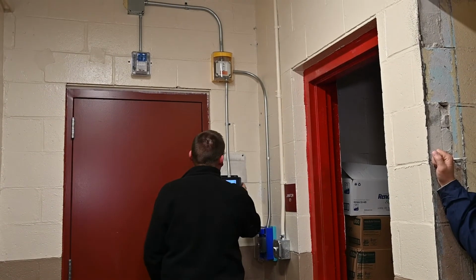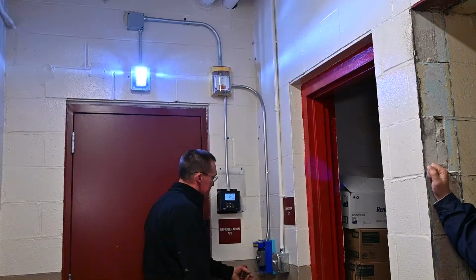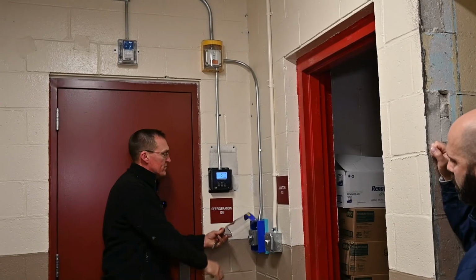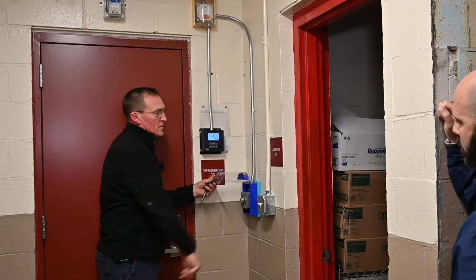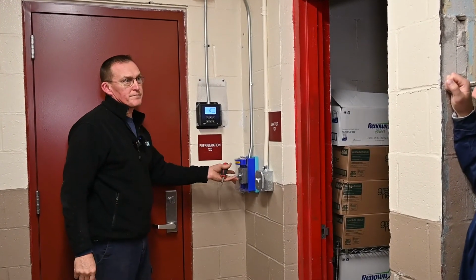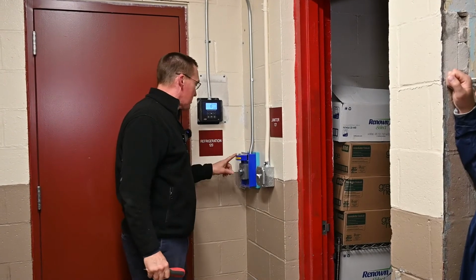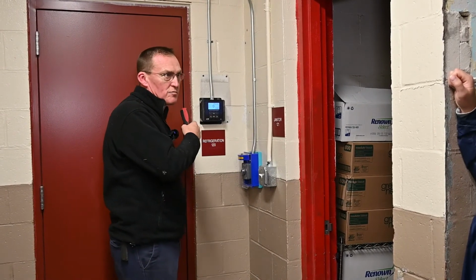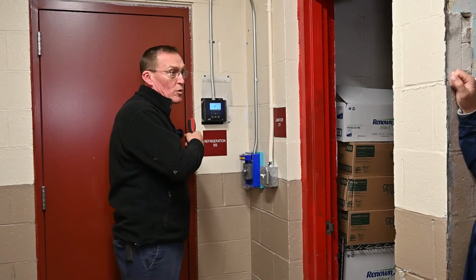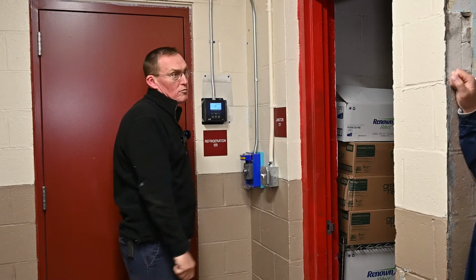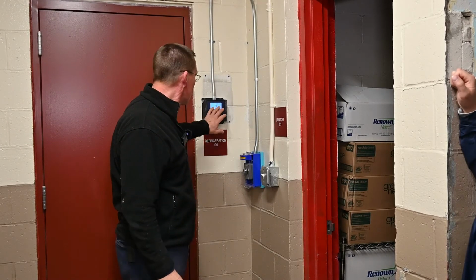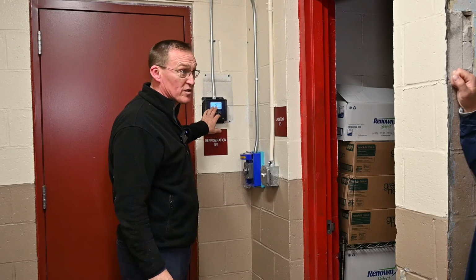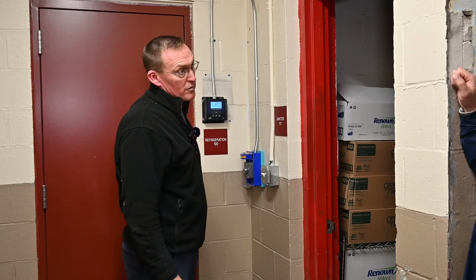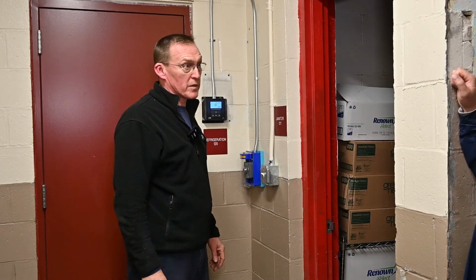If you have an alarm, if it does test out, it's interlocked. You have to clear it. When that detector goes off, the exhaust fan in the engine room will start. The damper will open and the exhaust fan will run. Again, this should always read 0. Anything over 100 is going to trip and set the alarm off, okay?